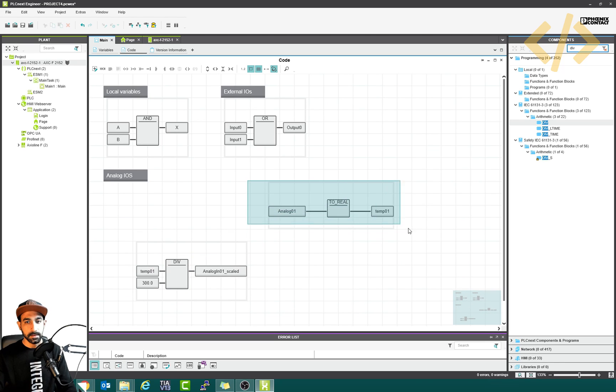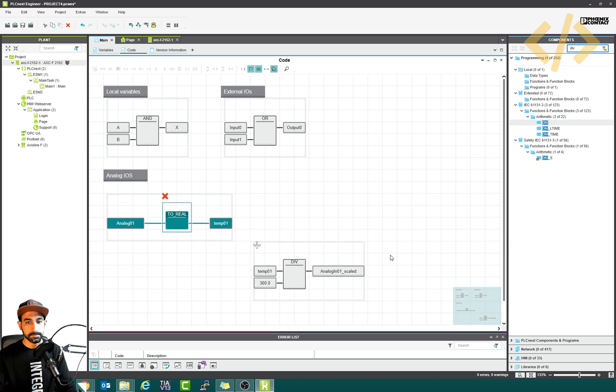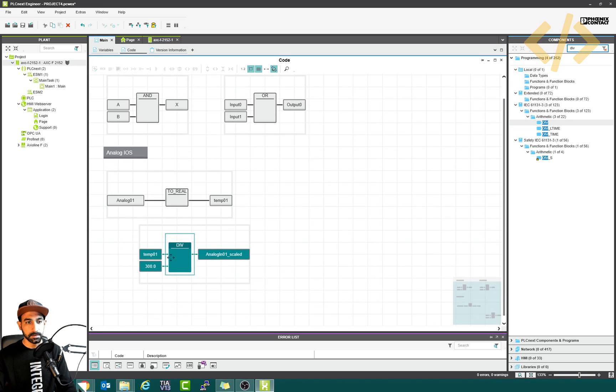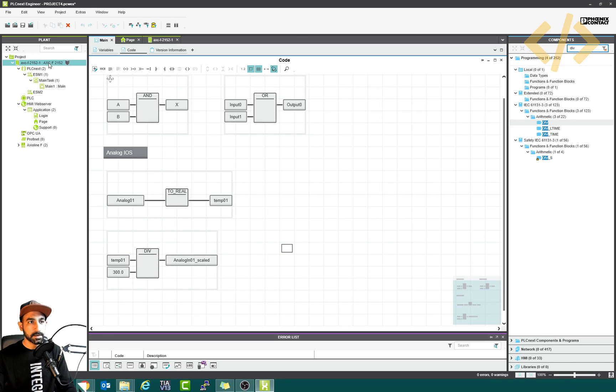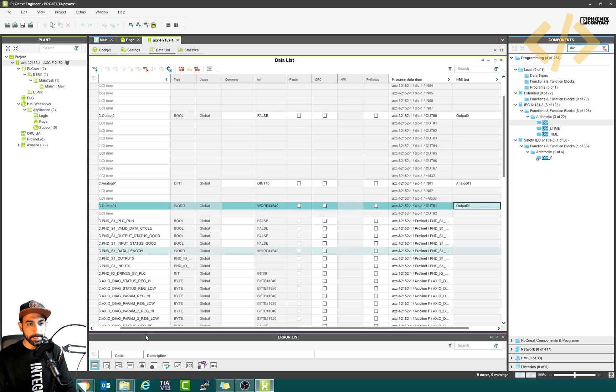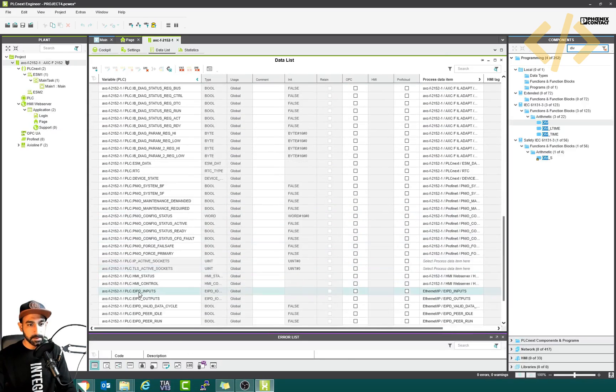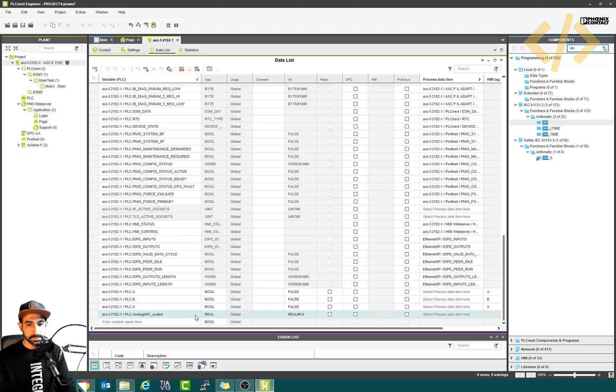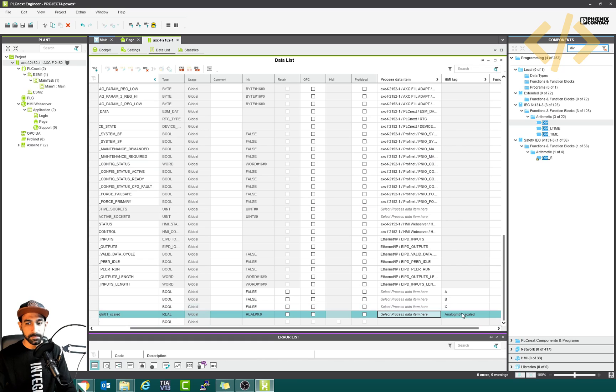Go back to my code and type my variable 'scaled' — the scaled value comes into this variable. This variable I want to show in the HMI. I go back to my PLC data list, and at the bottom I find the variable I defined: analog 01 scaled. This should be in the HMI — right-click and add HMI tag. So this is now coming into the HMI.